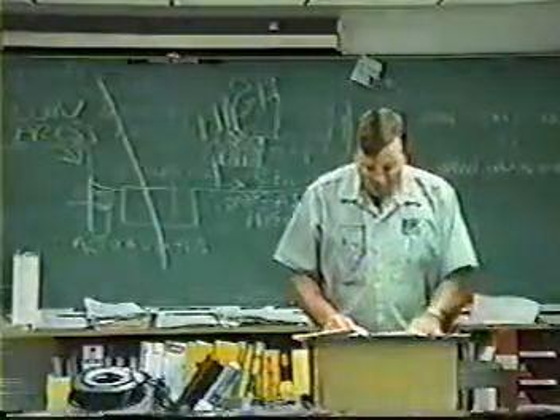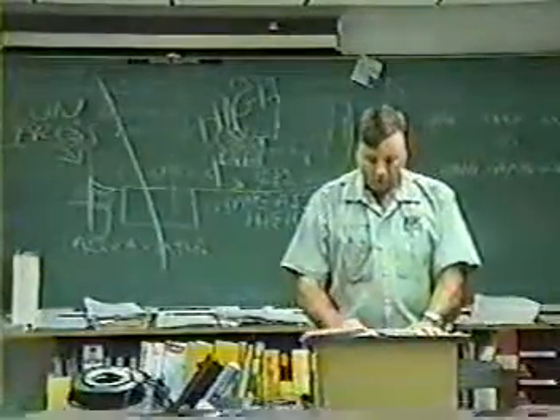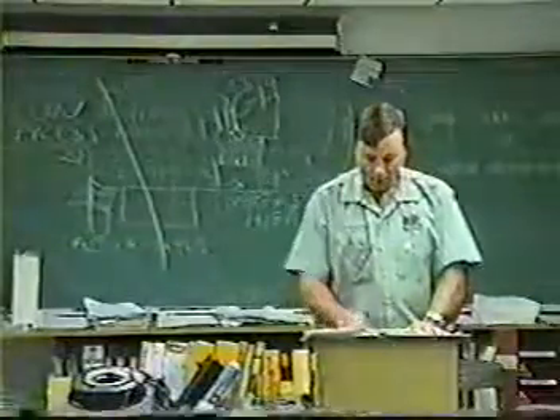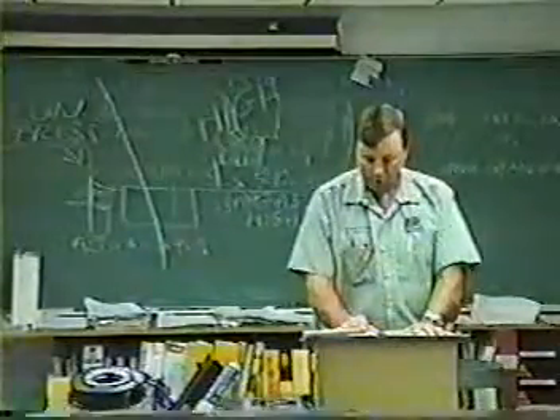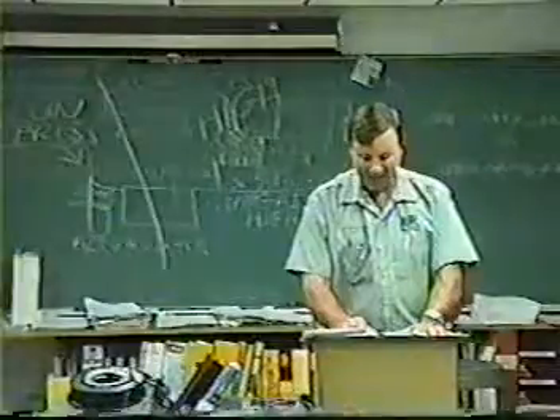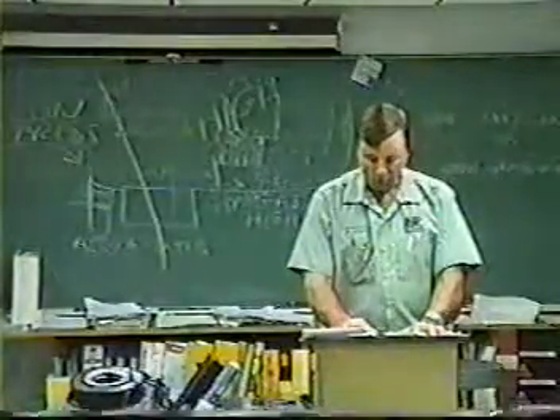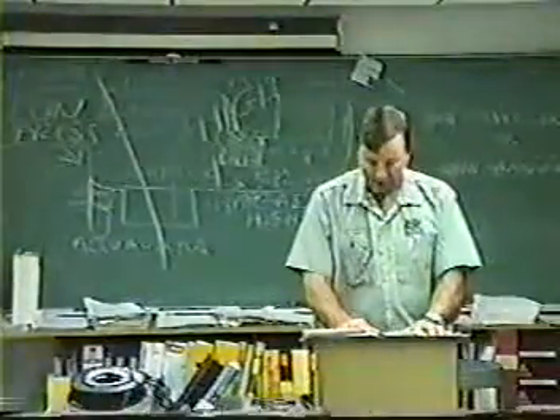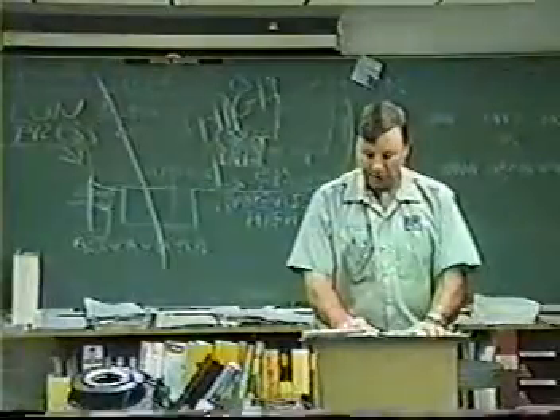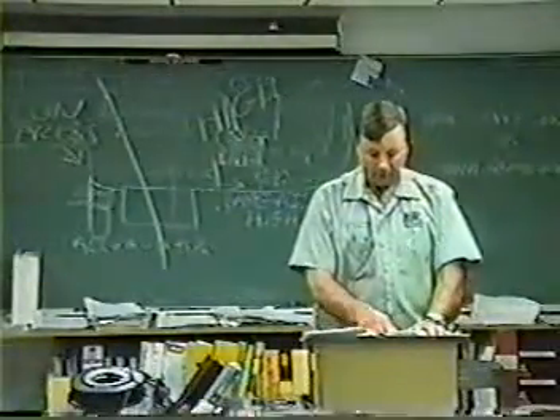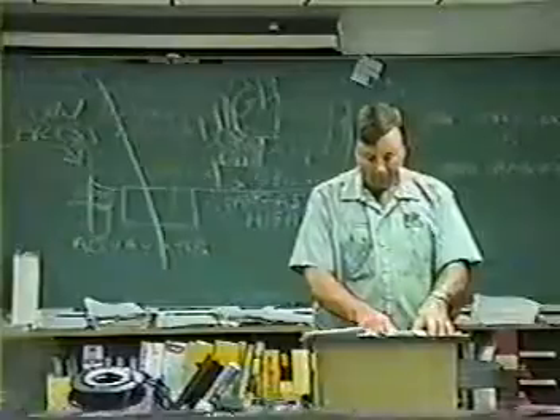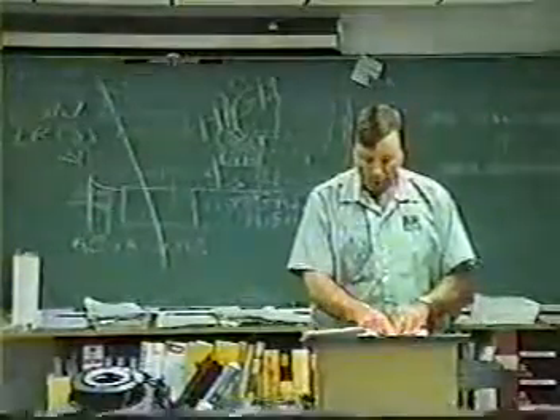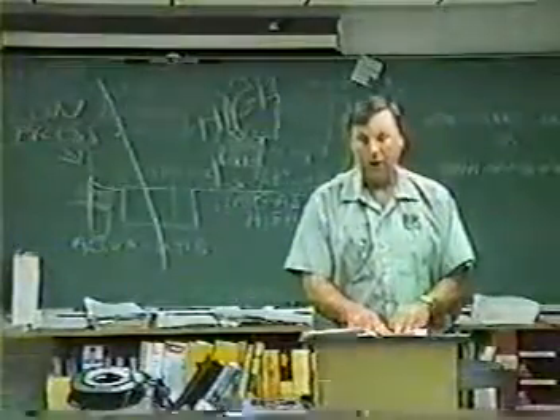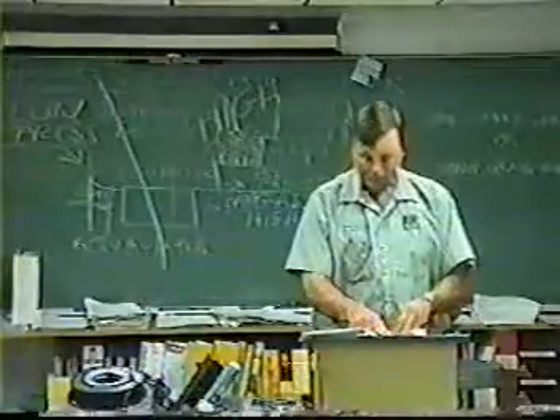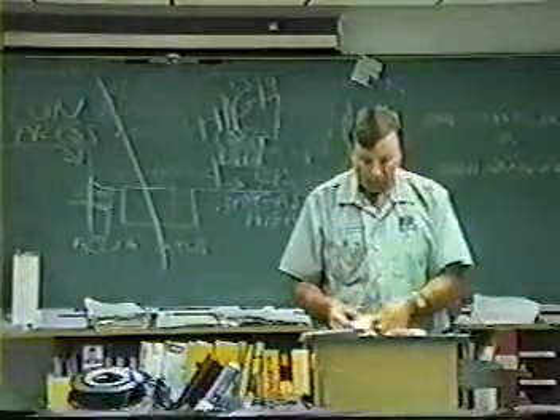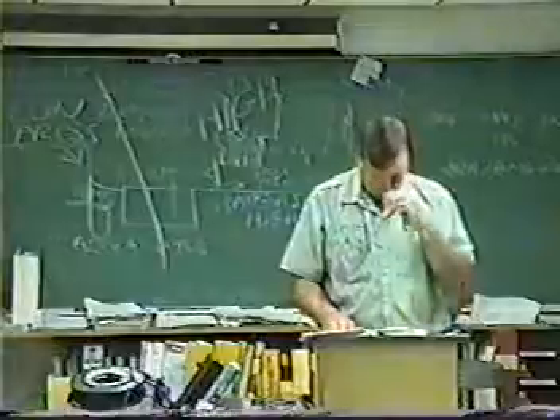Technicians maintaining, servicing, repairing, or disposing of low pressure appliances must be certified as a Type 3 technician or a universal technician. Disposing of low pressure appliances. Low pressure appliances being a chiller. Leak detection. A low pressure system operates below atmospheric pressure. That's the reason why they call it low pressure, because it operates in a vacuum. And we covered that a while ago on our PT chart.